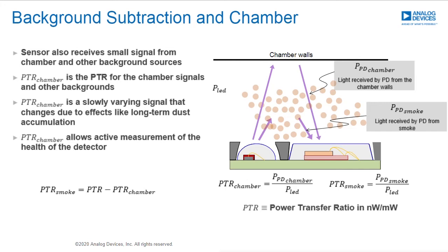So this introduces a couple of challenges, namely that you design a chamber that really reduces this background response to a level that is going to be relatively insignificant when you're trying to measure this small smoke signal that's there at the same time as this background response. So some of the things that have to be done here at the system level now is to actually null out that background response, which we call here a background subtraction.